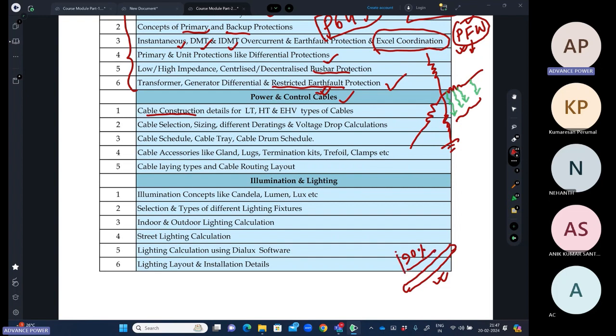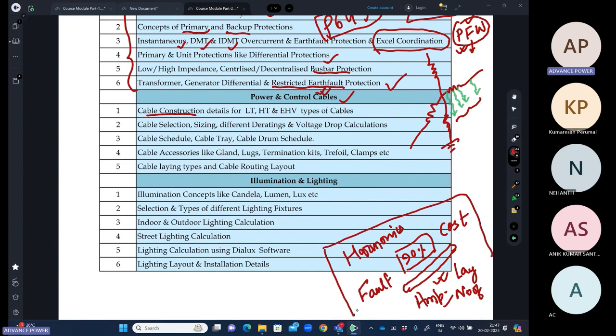You know your requirement, you know your cost, you know your fault level in your system, you know your ampacity in the system, you know how you are going to lay this cable, you know the number of cables you are going to lay, you know what harmonics are present in your system. What the manufacturer will give you is the ampacity of the cable at different derating factors. So what will be the different derating?